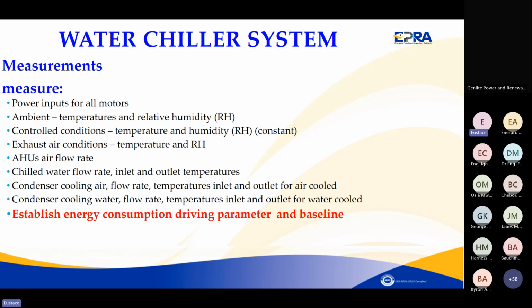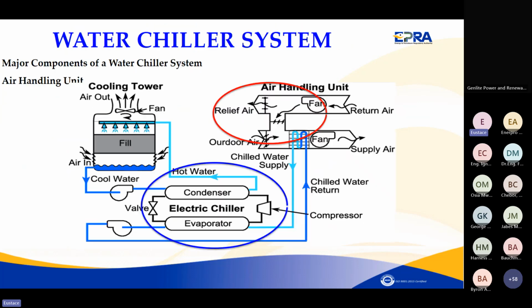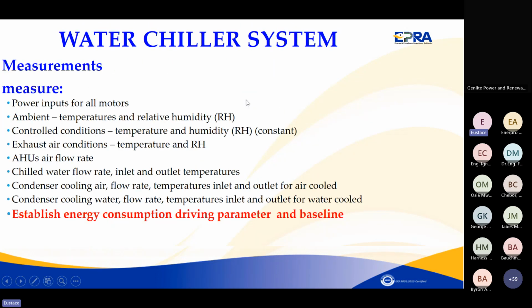Because those electronic equipment operate best at specific operating points, say 21 or 20 degrees and relative humidity of 50%, for the exhaust conditions you need to measure the relief air and see how those temperatures or conditions compare with the ambient and controlled conditions. That gives you an indication of the cooling load at that particular instant.